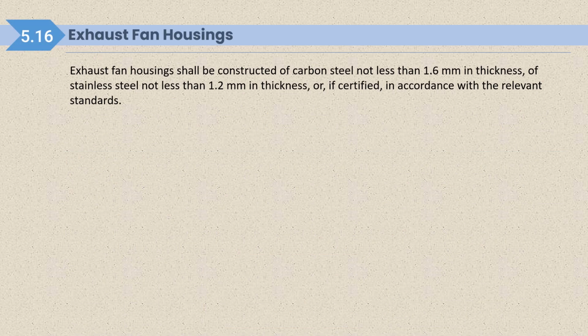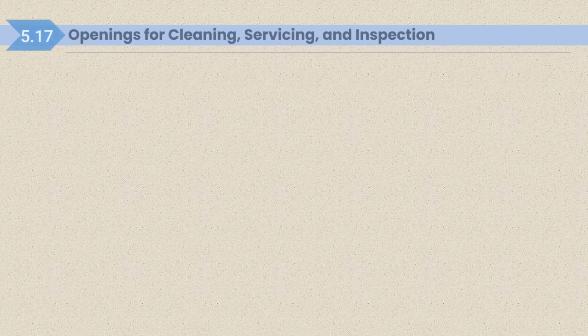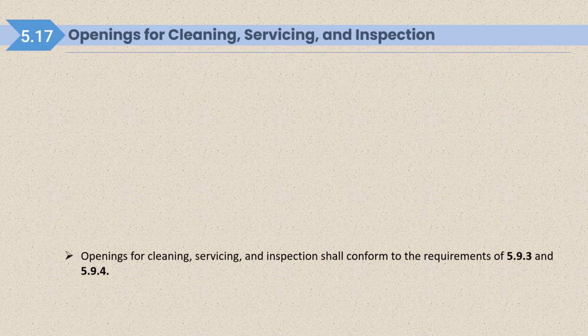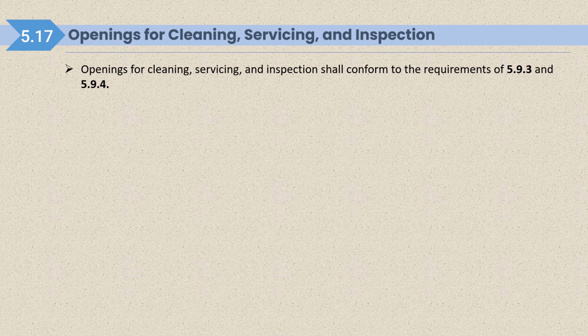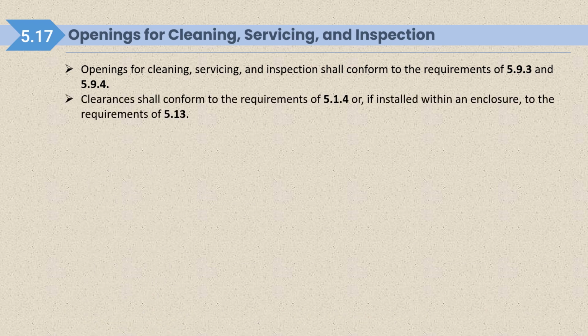Exhaust fan housing shall be constructed of carbon steel not less than 1.6 mm in thickness, of stainless steel not less than 1.2 mm in thickness, or if certified in accordance with the relevant standard. Opening for cleaning, servicing and inspection, that we have already discussed in previous slide. Clearance shall conform to the requirement. This is also covered.